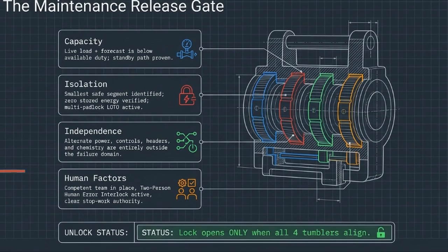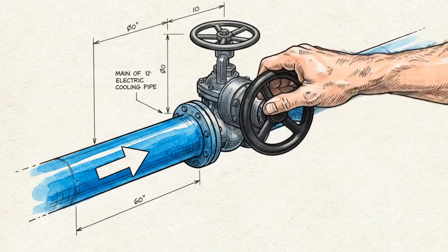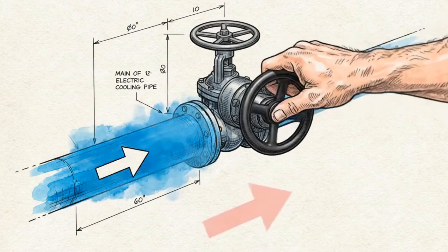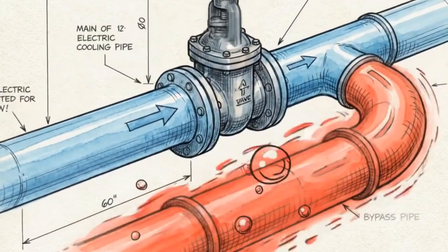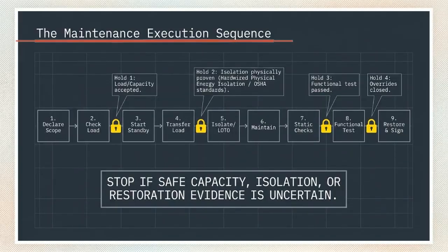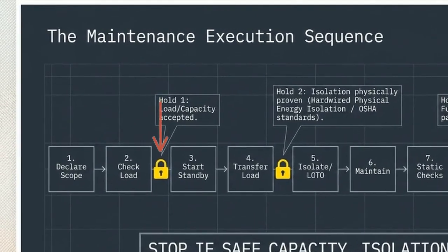Stripping away mechanical redundancy to perform maintenance introduces immediate vulnerability. Protecting the live IT load requires deterministic, unyielding physical and procedural gates. Once approved, work follows this 9-step maintenance execution sequence. Yellow lock icons denote rigid hold points, where operators must stop and verify safe capacity and isolation before proceeding.